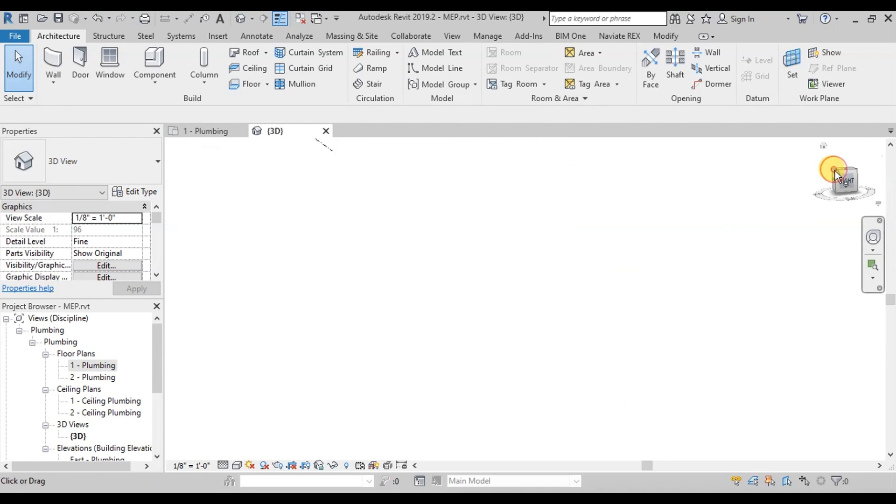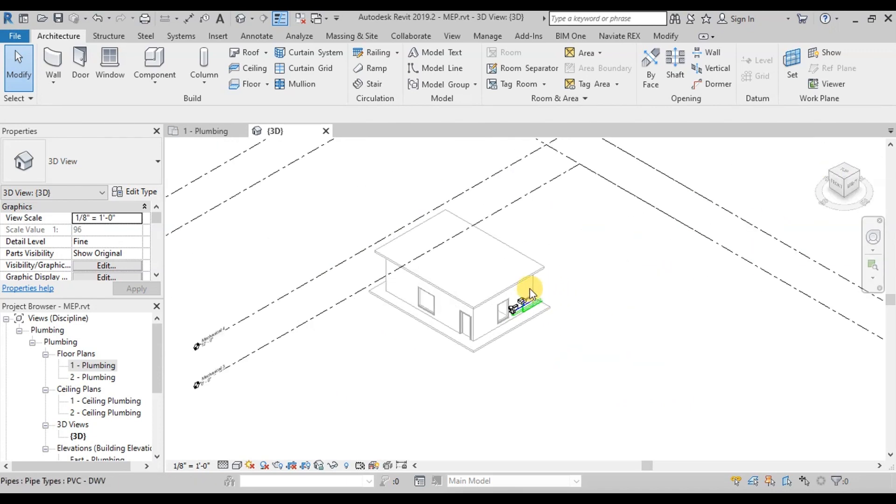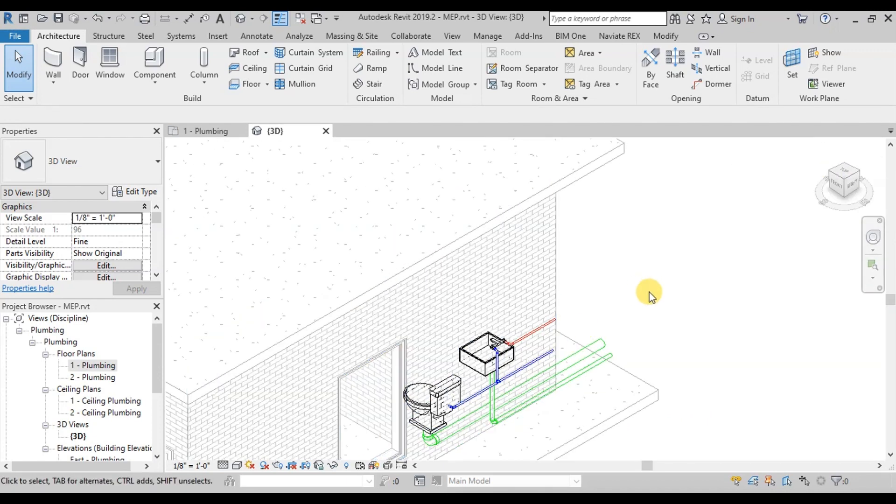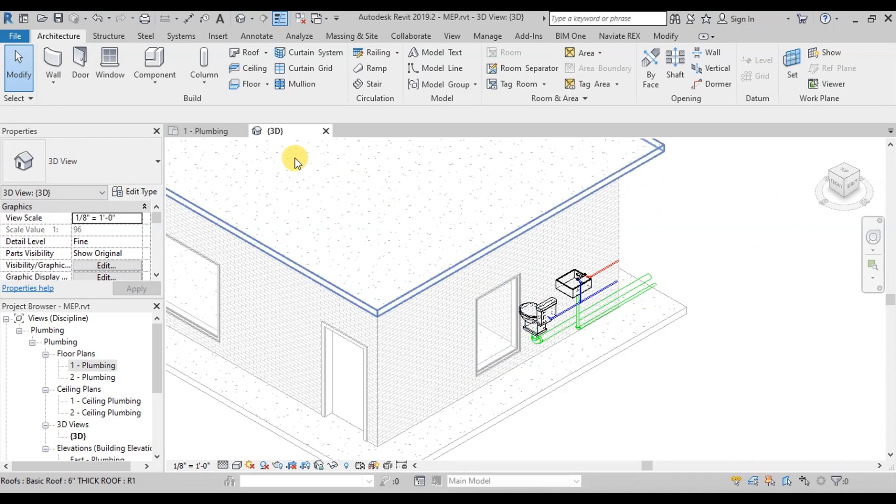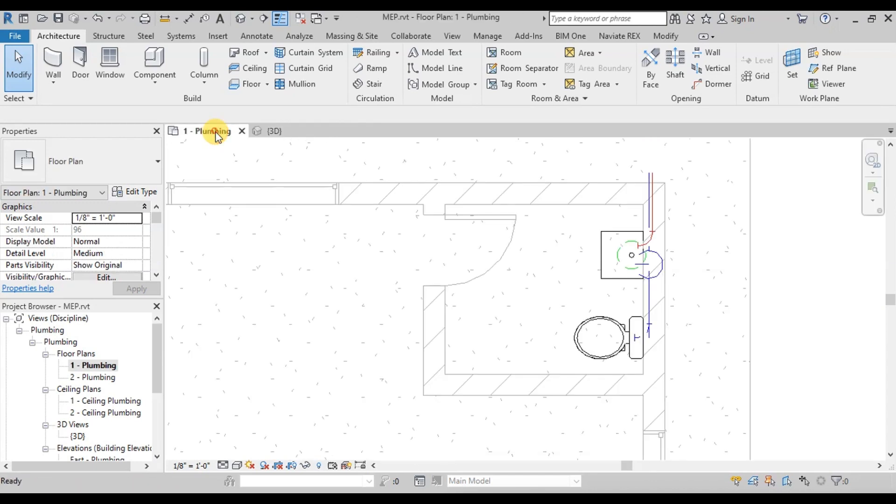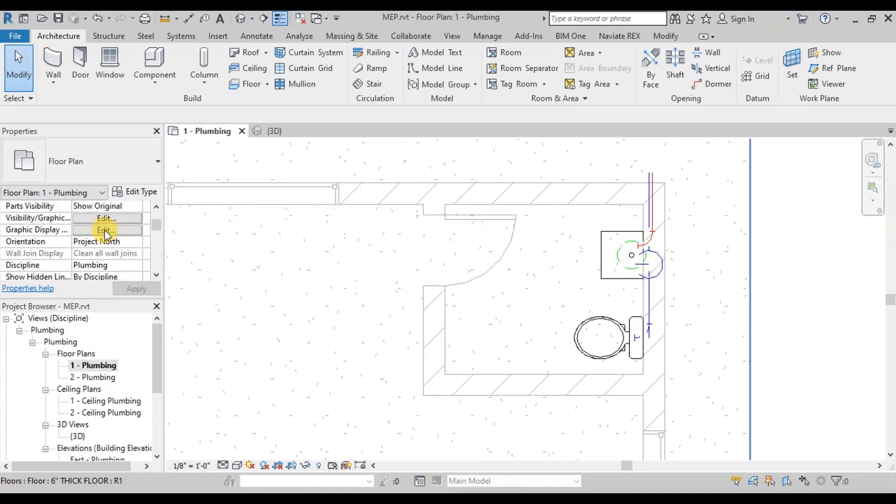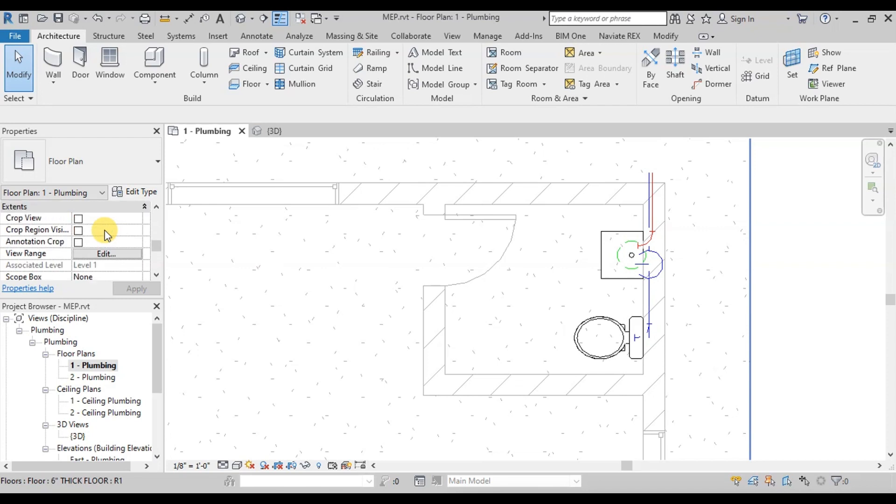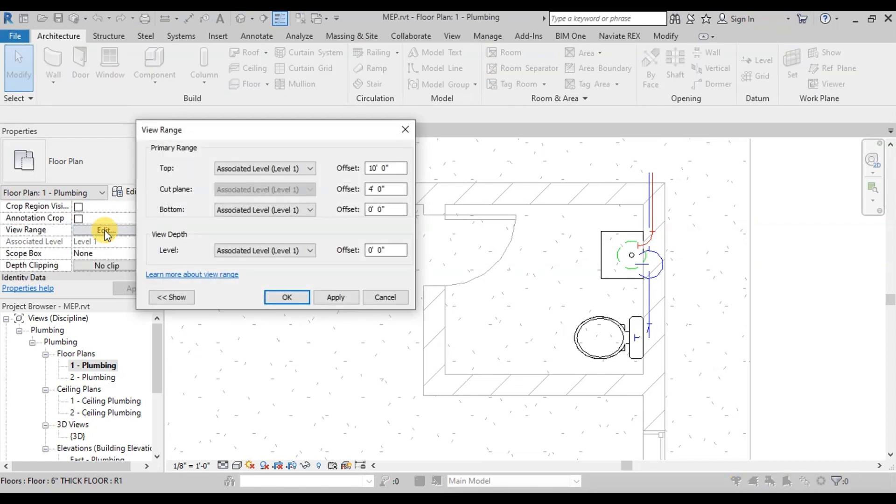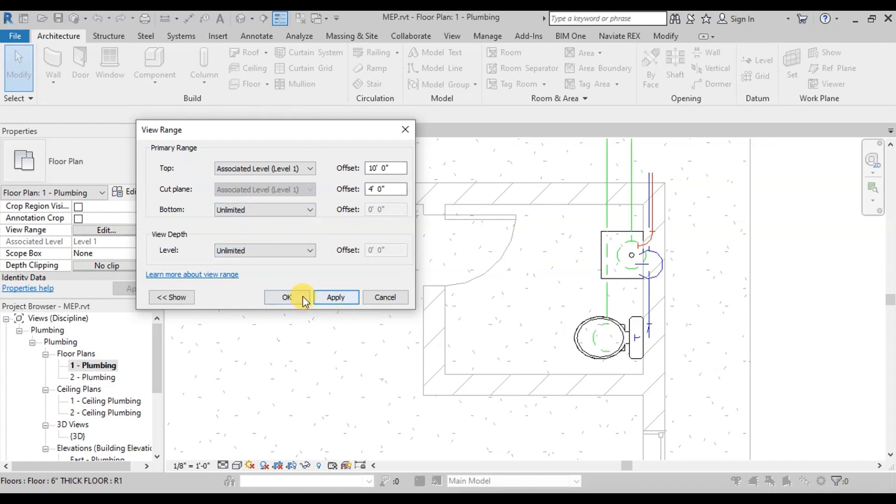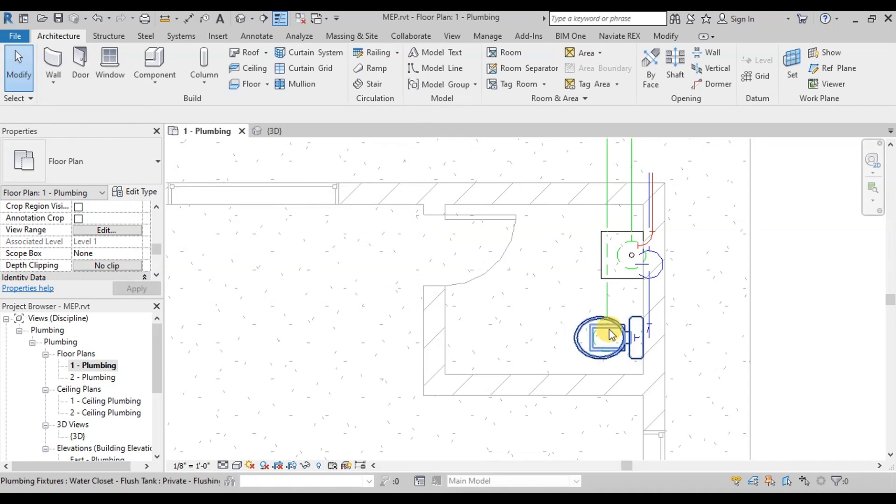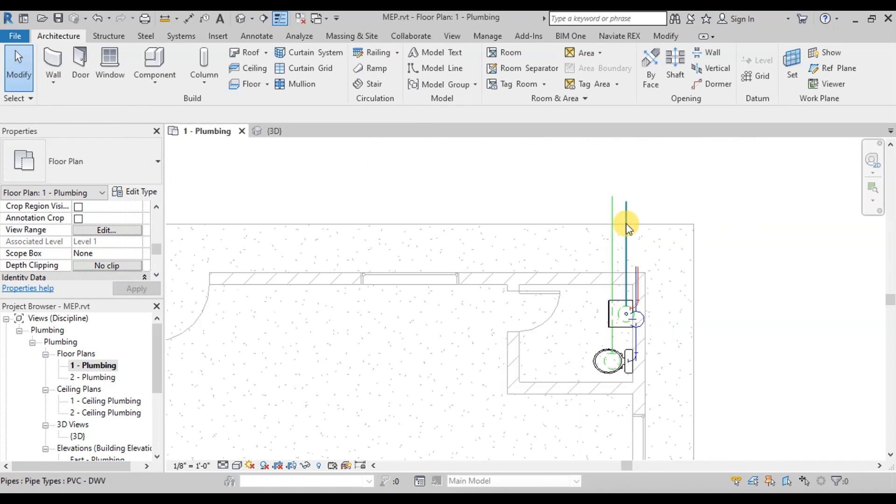We have completed our pipelines. Now let's view it in plan view. We are unable to see our sewage and waste water lines here. Go to Properties of this plan and then go to View Range Settings. Change the bottom to Unlimited and View Depth to Unlimited. Now these pipelines are visible.